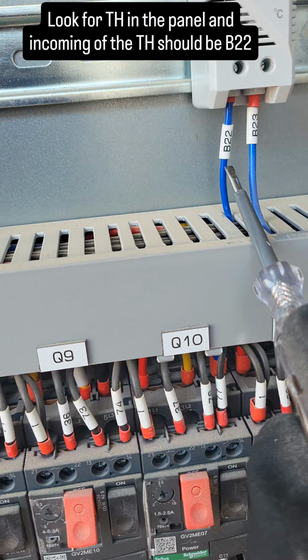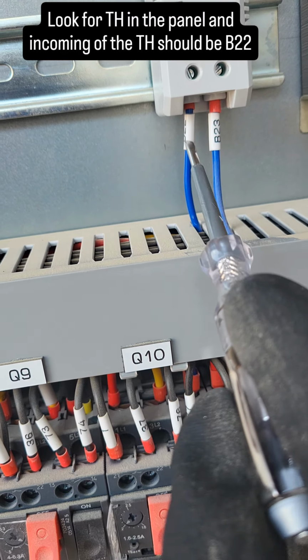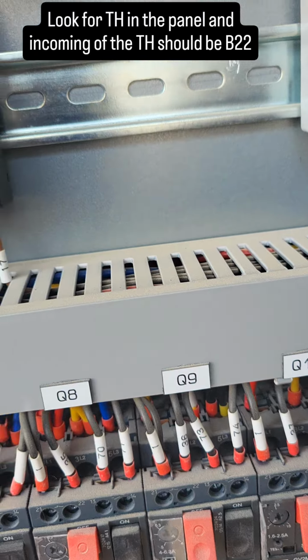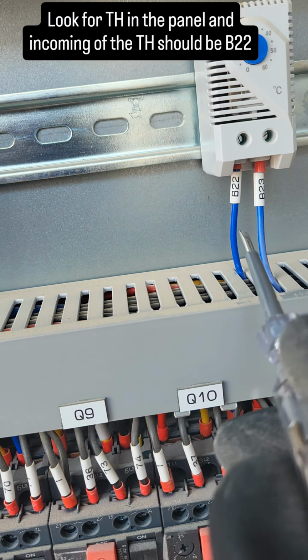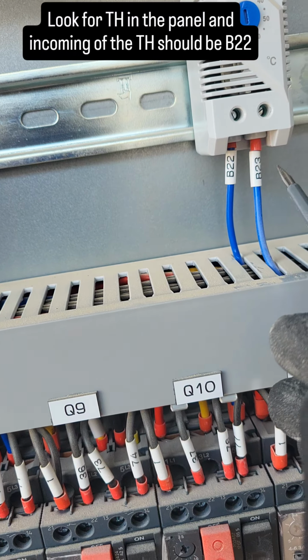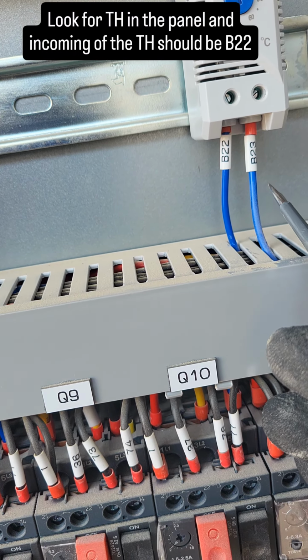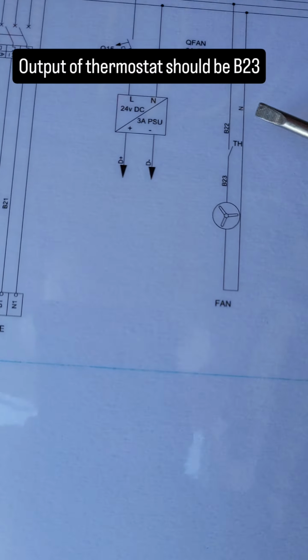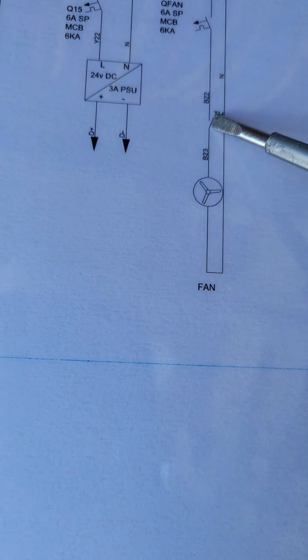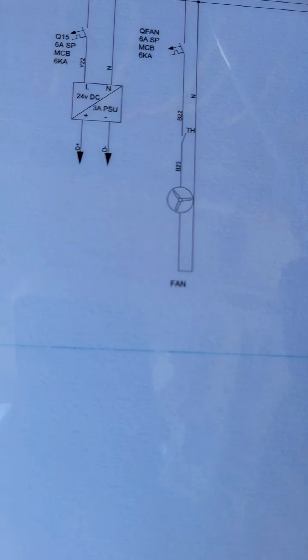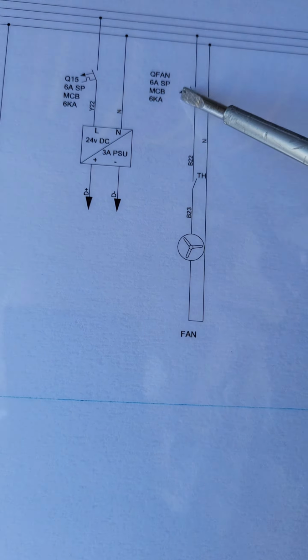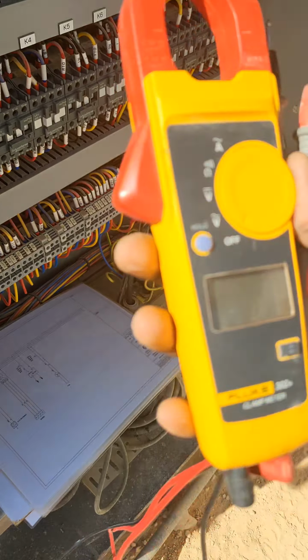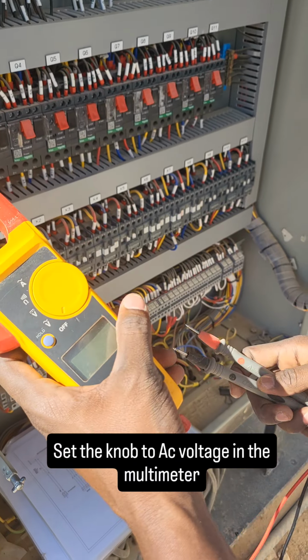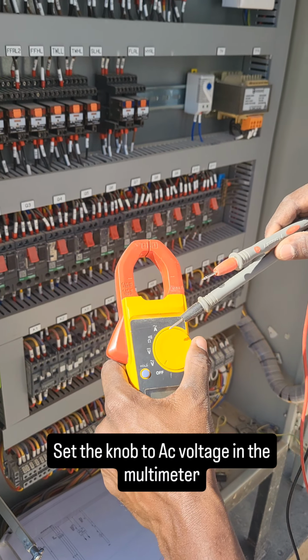So the input of the TH should be B22, which comes from the output of the MCB. So you can see the wire number B22 comes to TH, and the output should be B23 as mentioned in the drawing. See, the output wire number is B23, and the other end of the fan is directly connected to the neutral. Now we require a multimeter, and I will turn the knob to AC voltage.